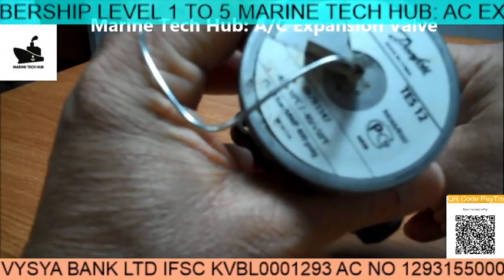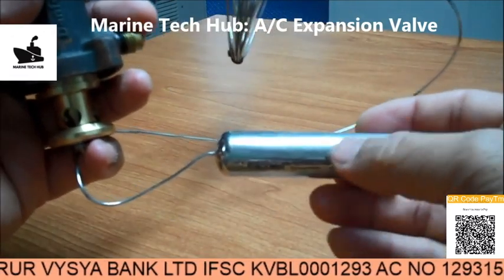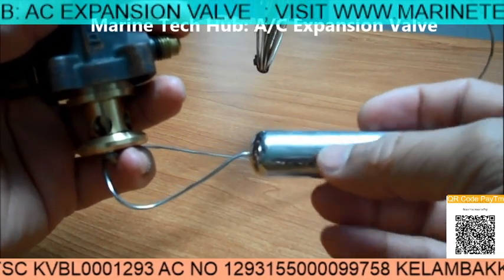This is the Danfoss Expansion Valve, model number TES 12. The range is from minus 40 degrees to plus 10 degrees, with a pressure range of 28 bar. What actually happens is this bulb contains liquid inside, which will expand and press the diaphragm here to operate the expansion valve.